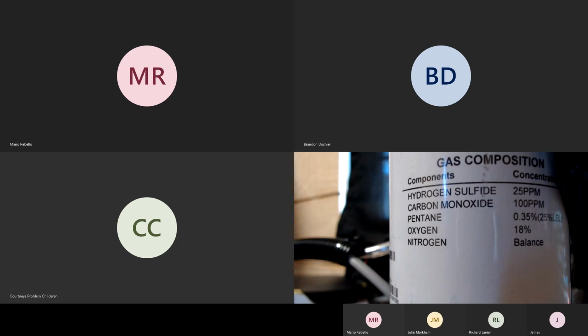And then whenever we're going to a call that we need the gas detector, we have a small bottle of gas that we just keep in the officer's seat. And the officer will turn the instrument on the way to the call and just turn the gas on and verify that all the alarms go off, so audible, visual, and vibrating, and that all the sensors respond, because that's all you're looking for. A bump test does not necessarily have to be done on a docking station. It can be done manually. So that's just something to remember with all that.